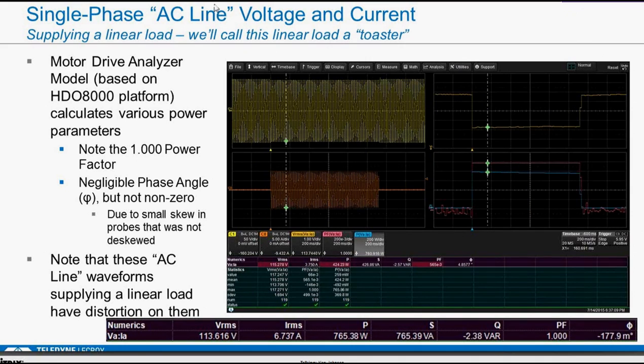And then this is actually a longer measurement now of that same thing. I've taken a several second acquisition, 2 seconds, and I've turned the toaster on, and the toaster starts generating heat through the coils here, and then it goes off, and the current goes to zero. And basically here I'm just showing what's happening with the power trend over time and all these different calculations. In this case, during this dynamic activity, the circuit behaves a little bit differently, and you don't necessarily have the same results at all times during the operation.